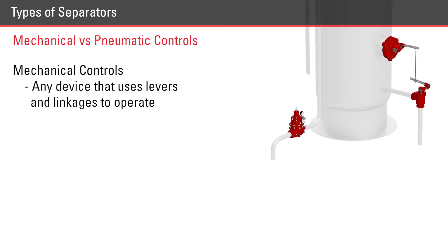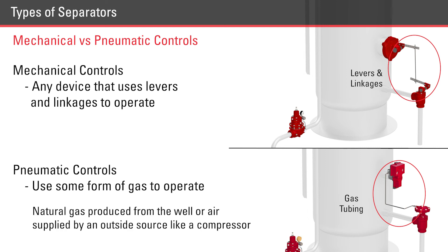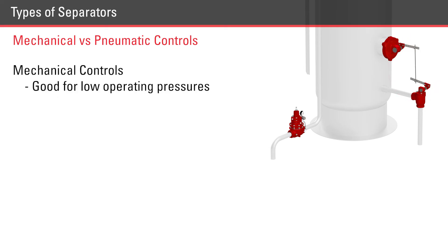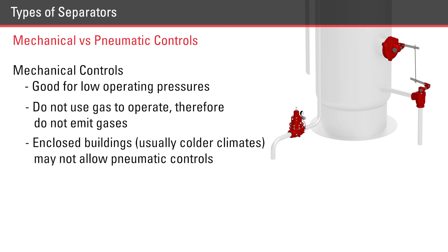We define mechanical controls as any device that uses levers and linkages to operate. Pneumatic controls use some form of gas to operate and control — these gases can be natural gas produced from the well or air supplied by an outside source like a compressor. If the operating pressure is low enough, mechanical controls are a great choice. Some regulatory agencies tightly control fugitive gas emissions, and mechanical valves don't use gas to operate, so they don't emit gas under normal operation. Enclosed buildings, usually found in colder climates, may not allow pneumatic controls to be used for safety reasons.